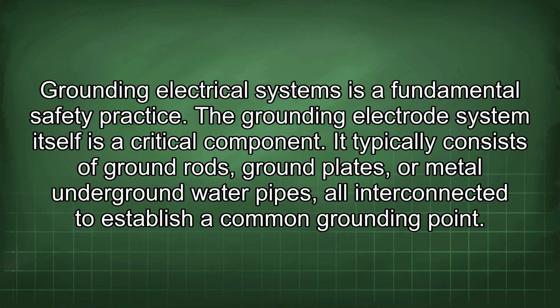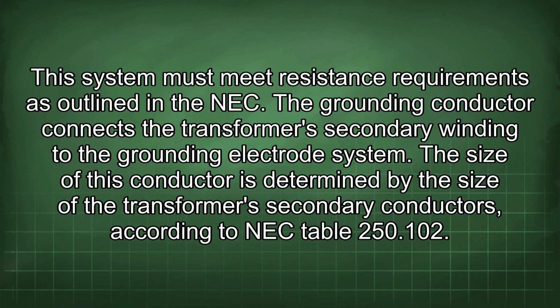Grounding electrical systems is a fundamental safety practice. The grounding electrode system itself is a critical component. It typically consists of ground rods, ground plates, or metal underground water pipes, all interconnected to establish a common grounding point. This system must meet resistance requirements as outlined in the NEC.